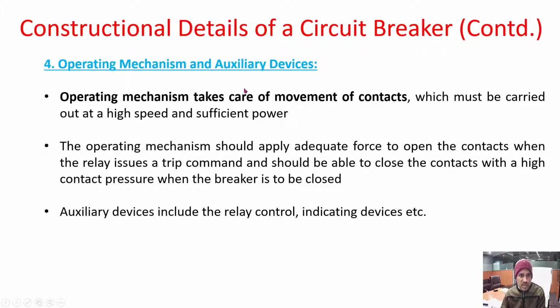And then operating mechanism and auxiliary devices. The operating mechanism takes care of movement of contacts. How the contacts will move is taken care of by this operating mechanism, which must be carried out at a high speed and sufficient power. So that's very, very important. The operating mechanism should apply adequate force to open the contacts when the relay issues a trip command.